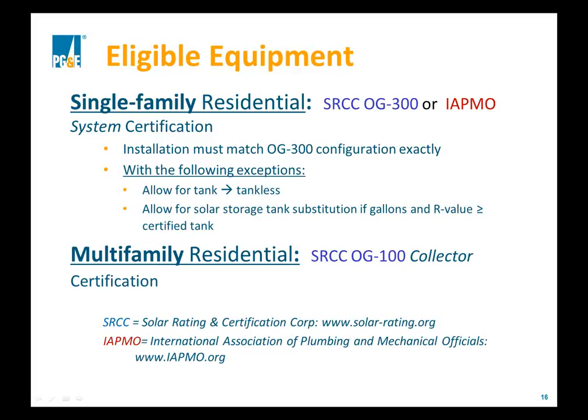Now, those OG300 package systems include collectors, and the collectors themselves receive a certification called OG100. So it makes sense that the smaller subcomponent is a lower number, and the package system is the OG300. For multifamily residential, the systems are built up. The entire package and system isn't necessarily certified, but the collector itself must have the SRCC certification. Both SRCC and IAPMO have online databases for looking up what systems and collectors are certified. That information is also available in the program calculator, which I'll demonstrate in a few minutes. Next slide, please.